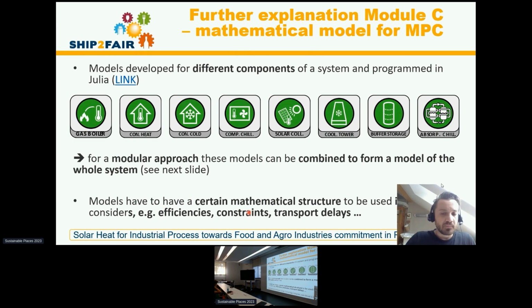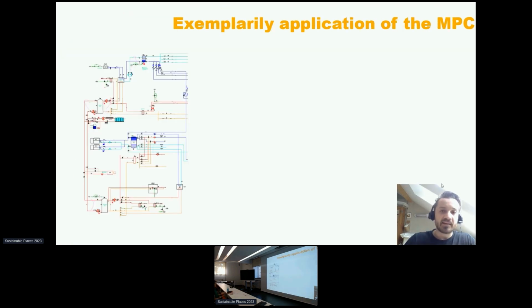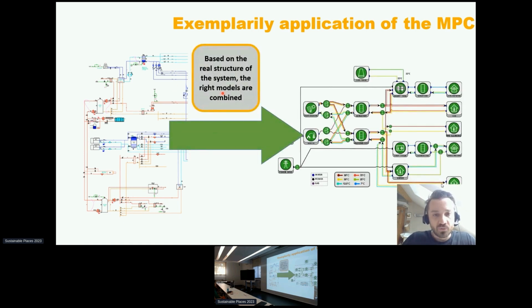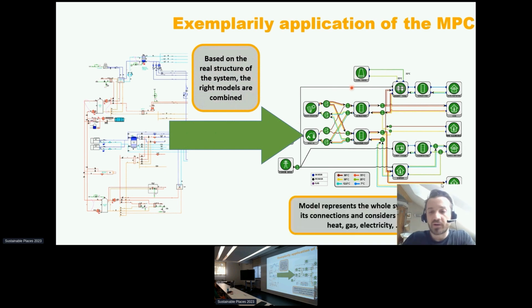This model has a certain mathematical structure which has to be used in the MPC, considering efficiencies, constraints, and transport delays. When we apply an MPC to a real system, we typically start with the piping and instrumentation diagram, and based on the real structure of the system, we combine the correct models to come up with a model representing the whole system and its connections, considering the prices for heat, gas, and electricity. So we have a simple representation of the whole system which should be controlled.